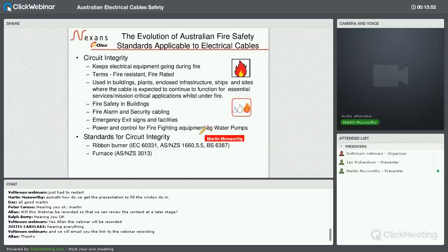The final key element of fire-rated cables is circuit integrity. So here we're talking about trying to make sure that cables keep working during a fire. Other terms that are commonly used to describe a cable which has got circuit integrity is fire resistant. Fire resistant cables, I guess it might not be understood that well, but you can get fire resistant cables that are not fire rated. All we really mean by that is a fire resistant cable would just have the circuit integrity element, but it may not necessarily have, say, the low smoke element.